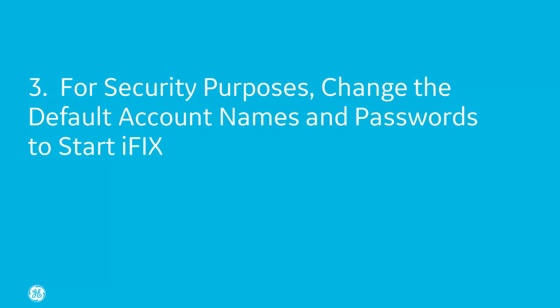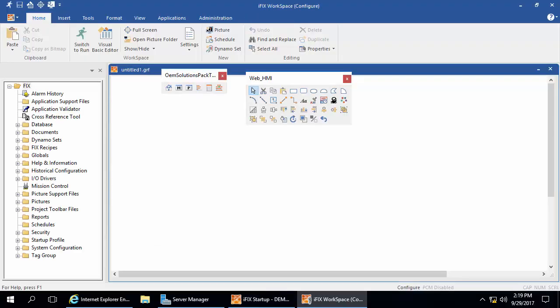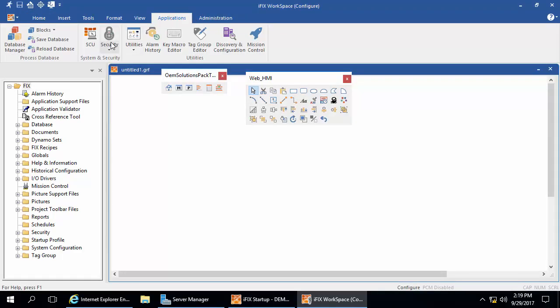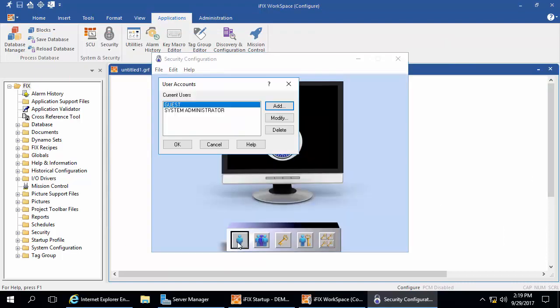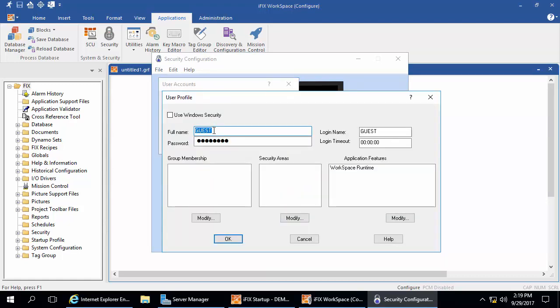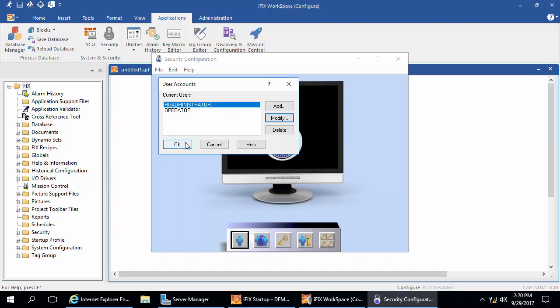For step three, for security purposes it's really important to go in and change the default usernames and passwords that come shipped with iFix. Start iFix — it's okay if it's in demo mode — open the workspace, click the application tab, then click Security, then Security Configuration Utility. Click OK. Next, click the users button in the toolbar, click the guest user, and then modify it. This opens the user profile dialog box. Change the default username and password and click OK. Next, click the system administrator, modify, and do the same thing. Click OK to finish, then save and exit the app.